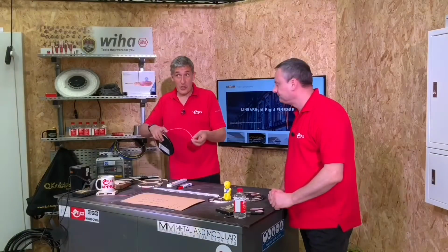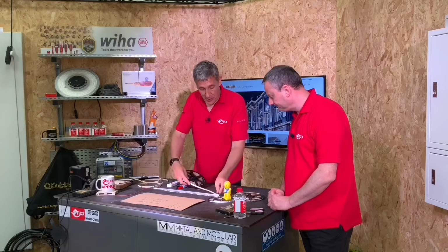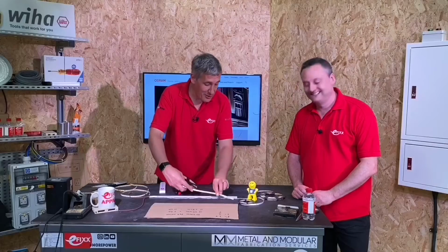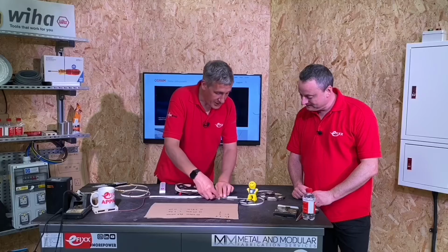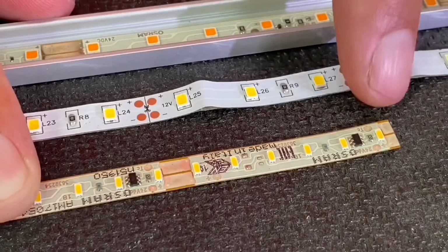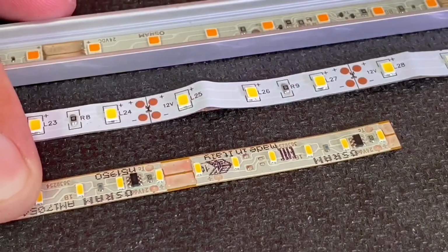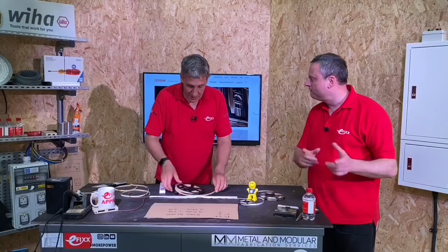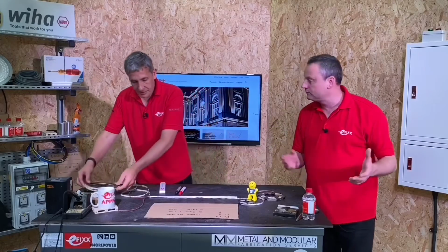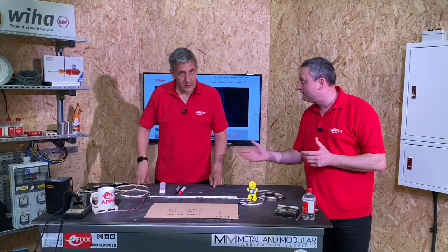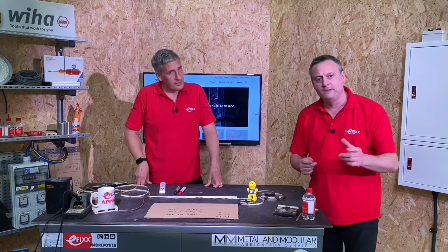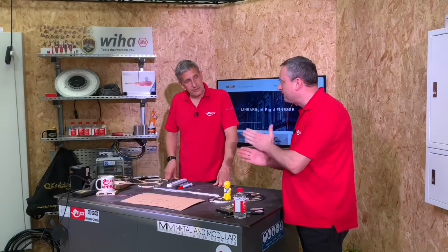So we bring in this short pitch LED, which short pitch actually means the LEDs are closer together. You'll notice on this one, there's now 6 LEDs between those 50 millimeter cut points. So we get the benefits of both with short pitch. We're at 24 volts, so we've not got as many issues with volt drop and therefore the light output dropping. But with the short pitch, we get those more frequent cut points as well.